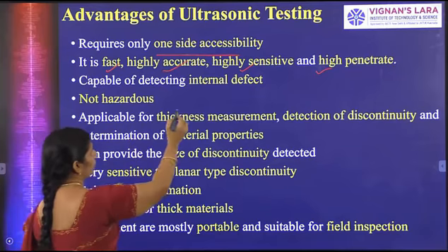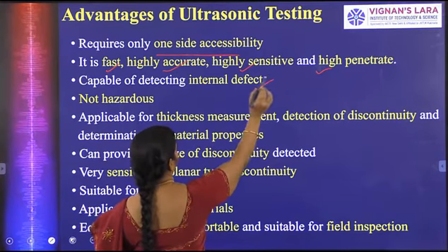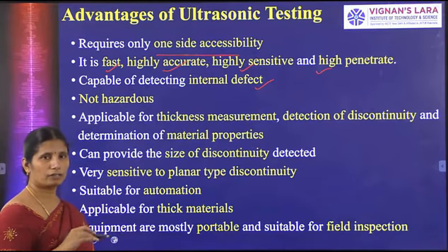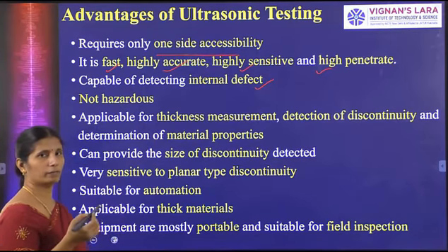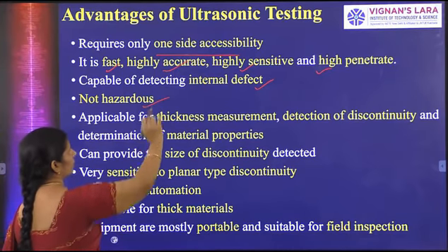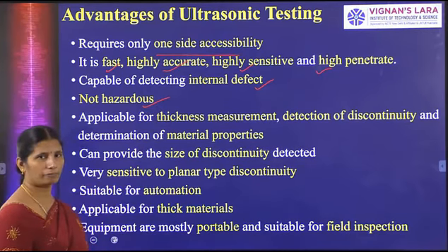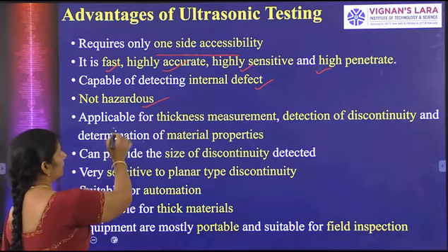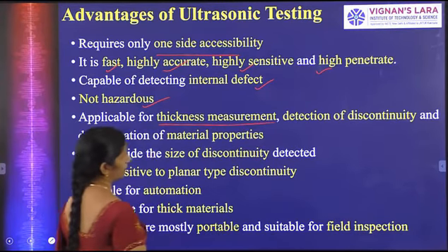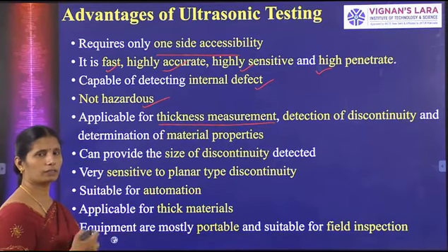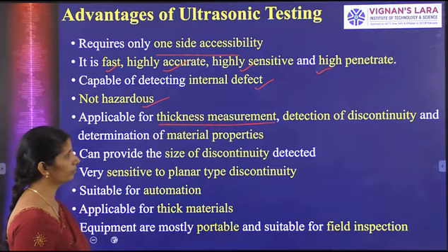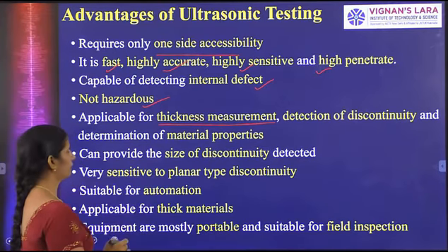They are capable of detecting internal defects, not only the defects present on the surface. They are not hazardous, not harmful, and applicable for thickness measurements. Not only the defects, we can measure the thickness of that material also, and detect discontinuities.